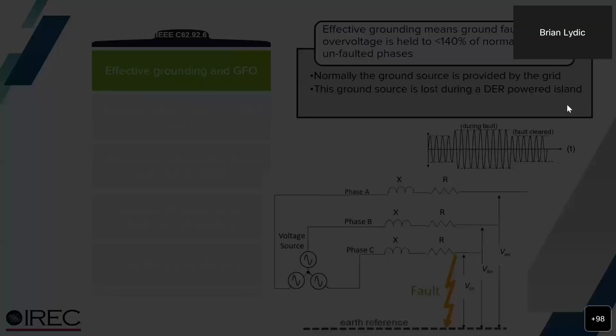So C62.92.6 basically deals with how inverter-based systems can be effectively grounded. And this starts to get a little bit technical, so I apologize if this is a little bit in the weeds, but effective grounding basically means that a portion of the distribution system, a portion of a circuit, is not subjected to overvoltages of greater than 140% of normal on unfaulted phases. And this typically happens with single line to ground faults.